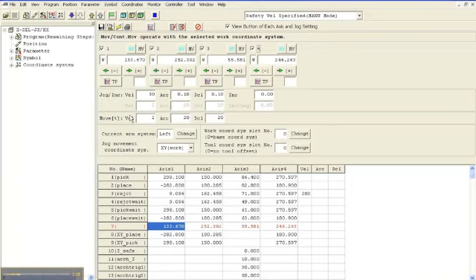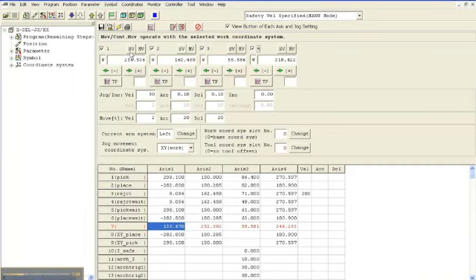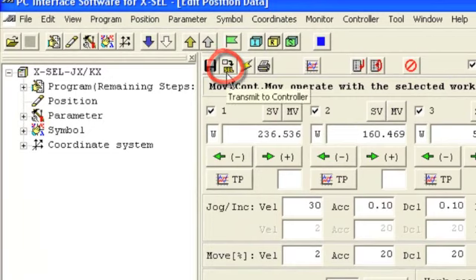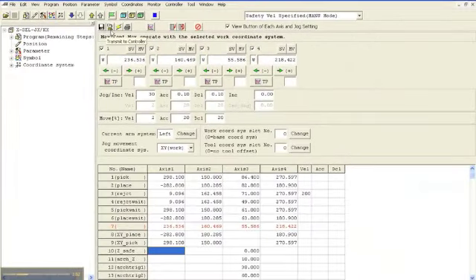The third method to teaching positions is to turn the servos off and position the actuator by hand. Since the power on the motor and encoder is separated, you can move the actuator with the servos off and the encoders will still follow the positions. You teach the positions the same way as in the second method. Once the change has been made, it will show up in red. To download it to the controller, press the Download to Controller button, which is always located right next to the Save As button.